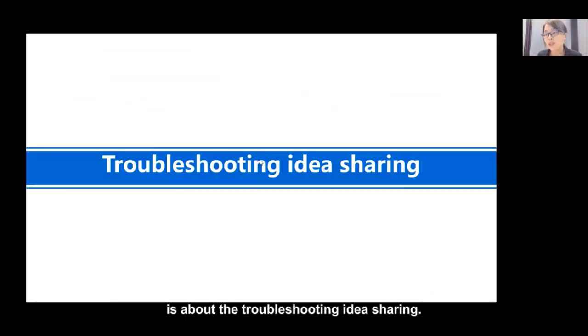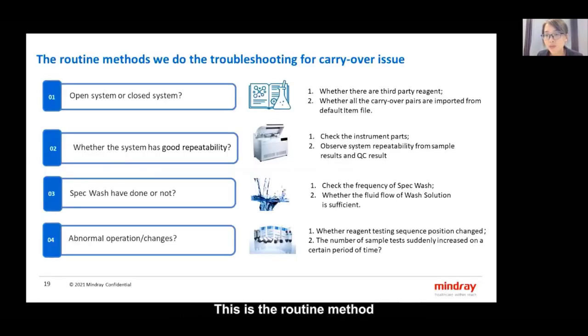The third part is about troubleshooting idea sharing. This is a routine method we use for troubleshooting carryover issues. When we receive a suspected carryover issue, there are 4 questions that we usually ask. Is it an open system or a closed system? Whether the system has good repeatability. Whether special wash has been done or not. Is there any abnormal operation or changes?